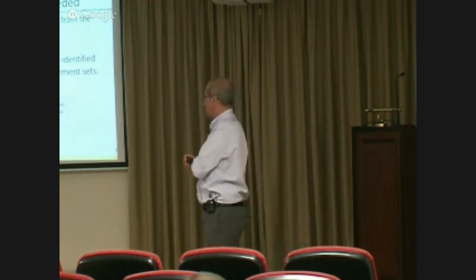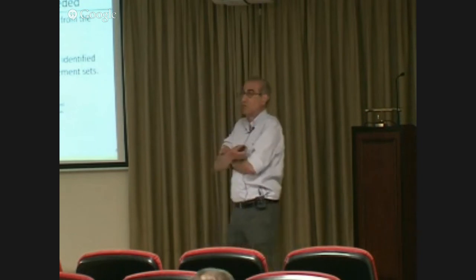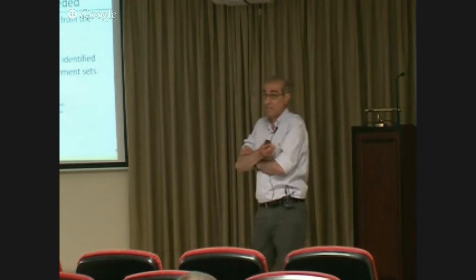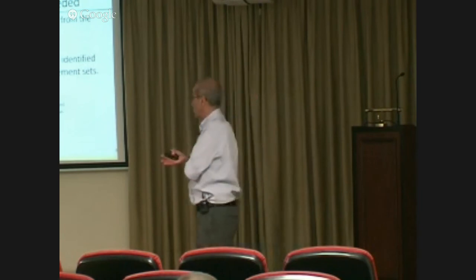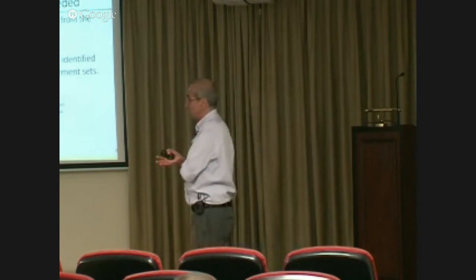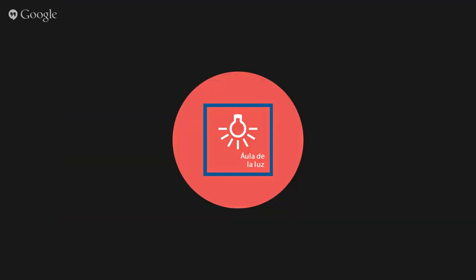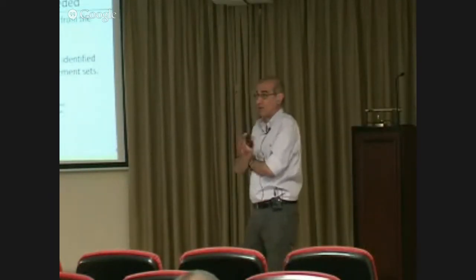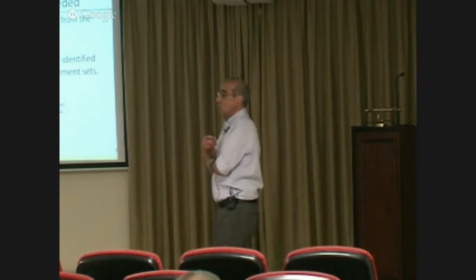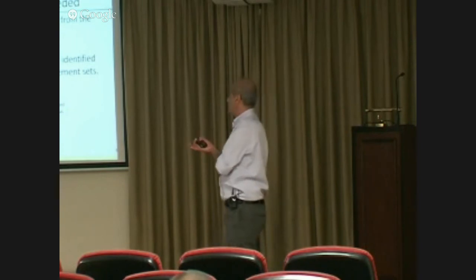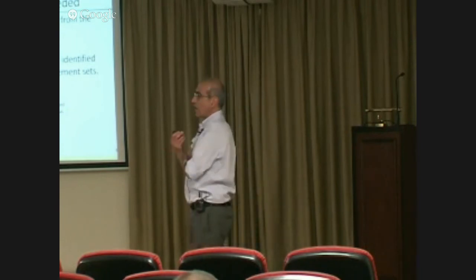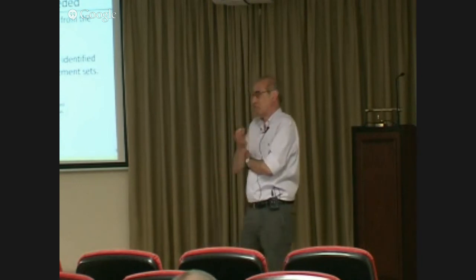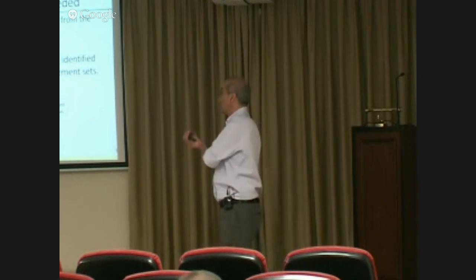Turns out this is a bad idea, because we don't know how PMUs are. Each and every PMU has a non-zero chance of being wrong, and if your reference is wrong, all other measurements will be wrong. So when you do state estimation, if you have access to PMU measurements, it's probably a must not to use a reference.